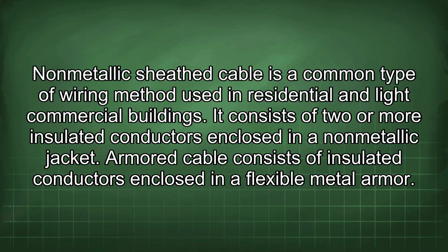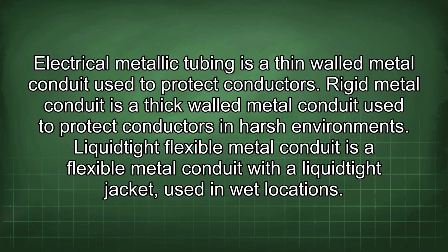Non-metallic sheathed cable is a common type of wiring method used in residential and light commercial buildings. It consists of two or more insulated conductors enclosed in a non-metallic jacket. Armored cable consists of insulated conductors enclosed in a flexible metal armor. Electrical metallic tubing is a thin-walled metal conduit used to protect conductors. Rigid metal conduit is a thick-walled metal conduit used to protect conductors in harsh environments. Liquid-tight flexible metal conduit is a flexible metal conduit with a liquid-tight jacket used in wet locations.